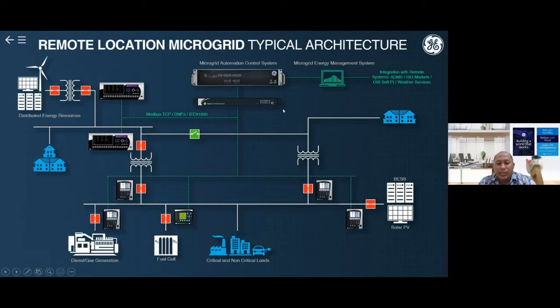If we look here, inside of the microgrid, it will consist of a few items. First is the controller. As we can see here, the black one is the microgrid automation control system. This microgrid controller will connect to each of the IEDs scattered on the power sources as well as the load. Each of the power sources as well as loads should be equipped with an IED. This IED can be supplied by GE, or it can use the existing IED already supplied with the existing power sources, and even on the load side it is possible to use the existing IED. And from all of these IEDs, it will connect to the microgrid controller.